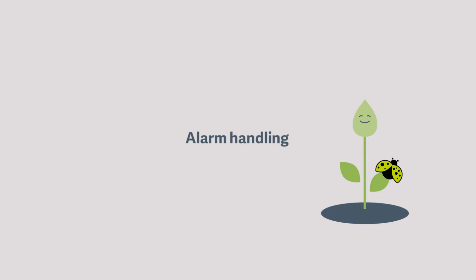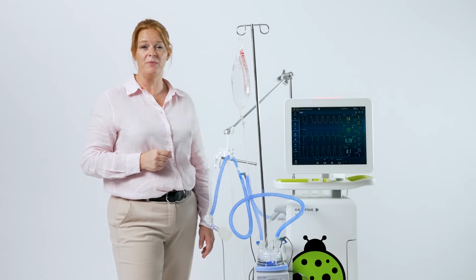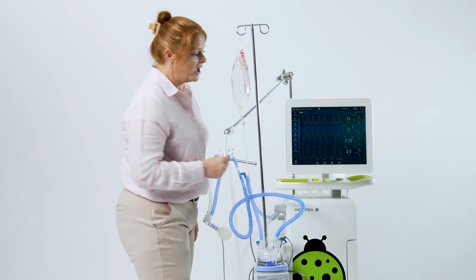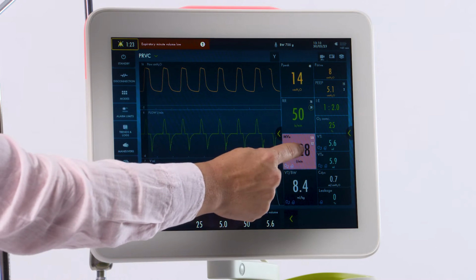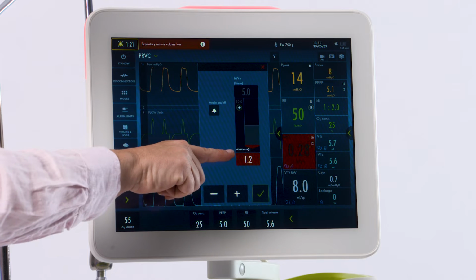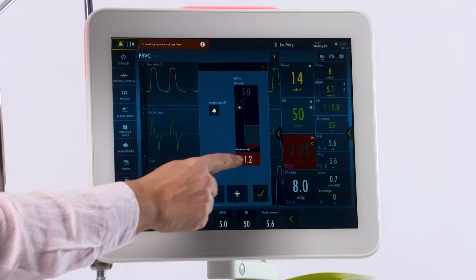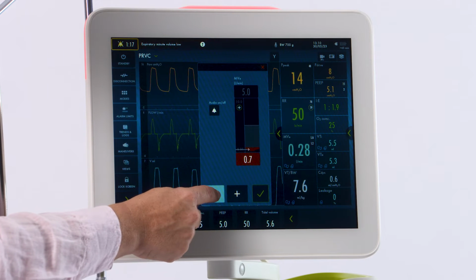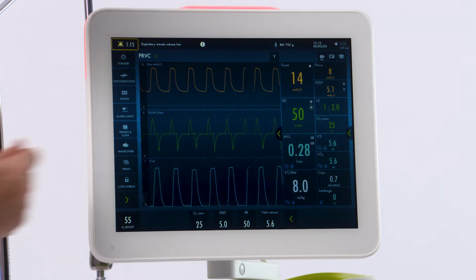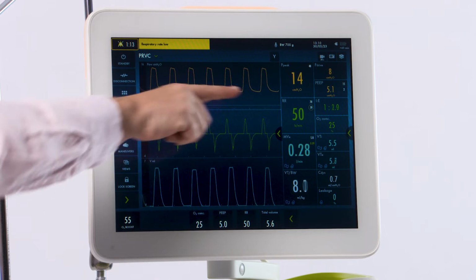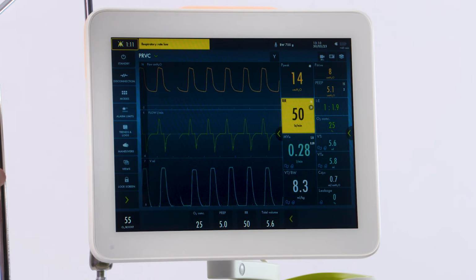There are 3 types of alarms: Red is high priority, yellow, medium, and blue, a low priority. As you can see over here, the low minute ventilation is alarming here. You can make the adjustment on the screen and hit your check mark to confirm. Same thing with the medium priority.